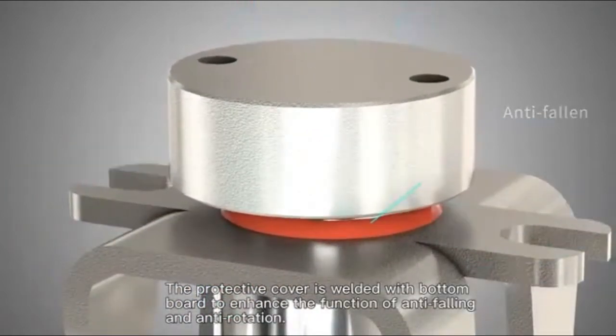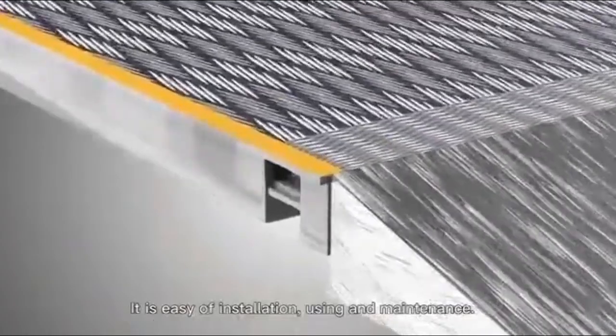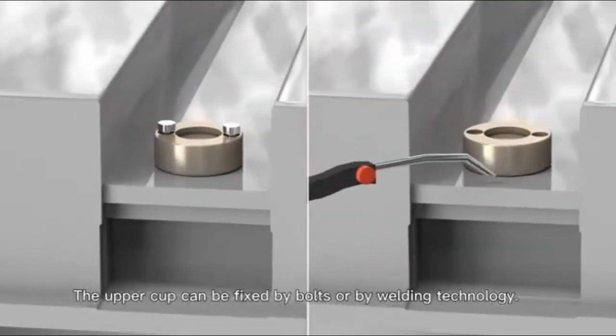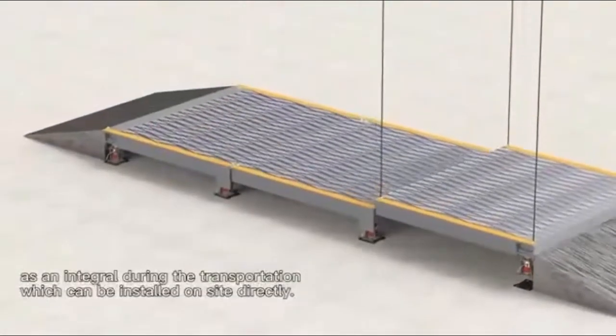It enhances the function of anti-falling and anti-rotation and is easy for installation, using, and maintenance. The upper cup can be fixed by bolts or by welding technology. The load cell can be fixed with a platform as an integral unit during transportation.